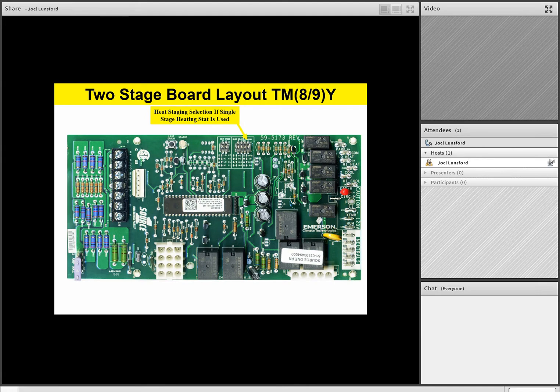So in the auto position, as the furnace comes on, the control board starts monitoring thermostat activity. In other words, how long does it take for the thermostat to satisfy on first stage? And then based on some intelligence that's programmed in on the board, it starts making intelligent decisions on when to bring in second stage. So I recommend put it in the auto position, because at that point you're allowing the board to optimize operation and comfort even if you're stuck with a single stage thermostat.